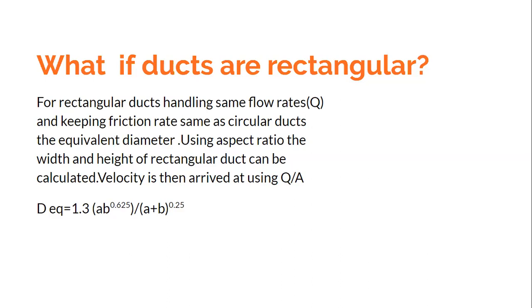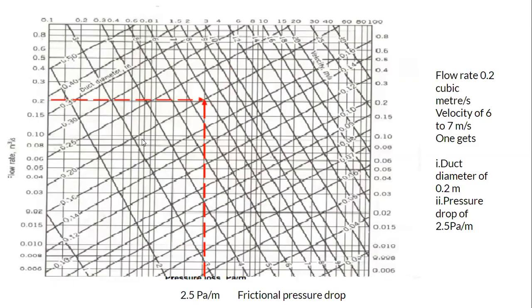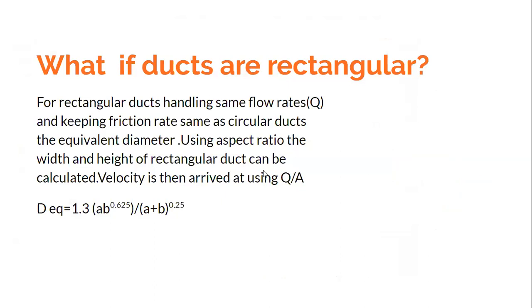One important caveat when using this chart for a rectangular duct: the velocity read from the chart — in my example, 6.8 meters per second — is not to be taken as the velocity for the rectangular duct. To find the actual velocity in a rectangular duct, you must take the flow rate Q and divide it by the area of the rectangular duct (Q/A). Do not obtain velocity from the friction chart when the duct is rectangular.